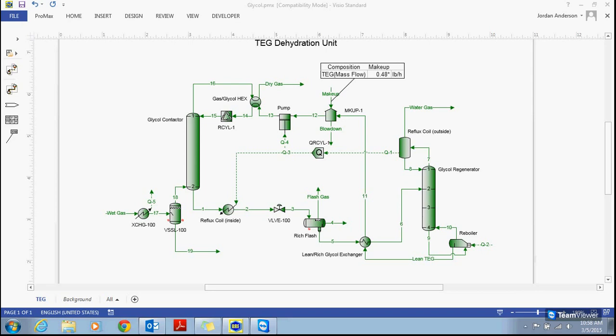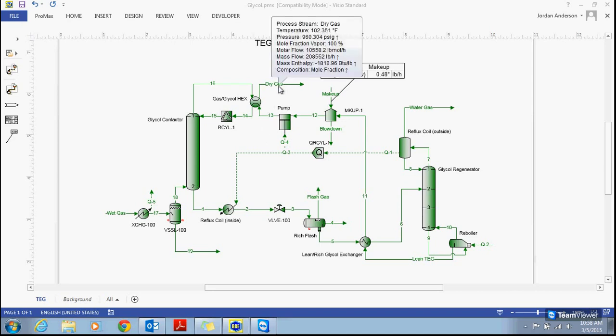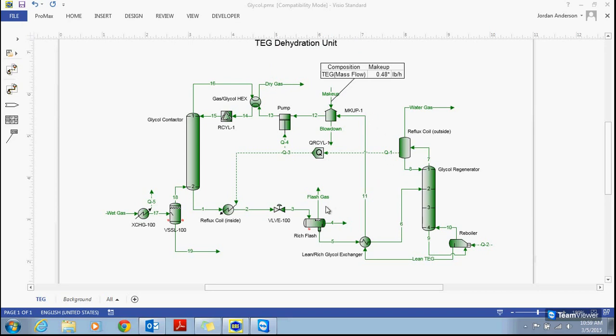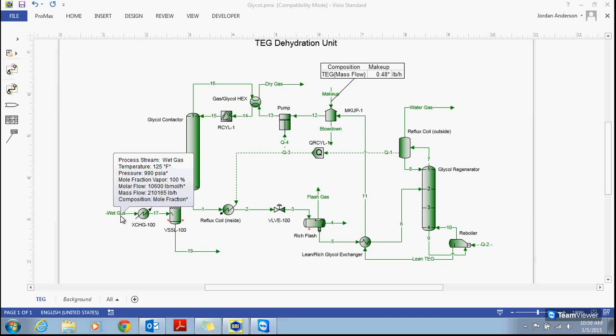In this system here, we're looking at a dehydration unit where we're circulating our glycol. In this process, we're always going to lose a small amount of glycol. We'll lose a little bit in our dry gas stream, some in our flash gas stream, and also some in the water gas stream coming out the top of our glycol regenerator. What we want to do in this example is sum up those losses.